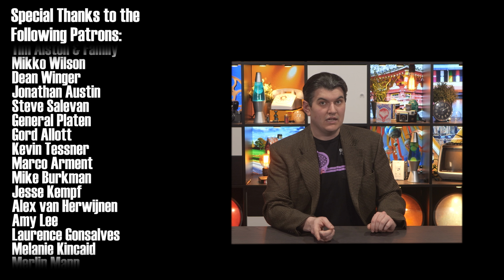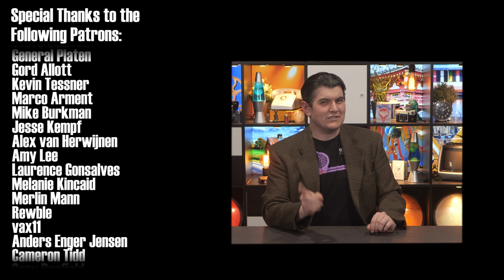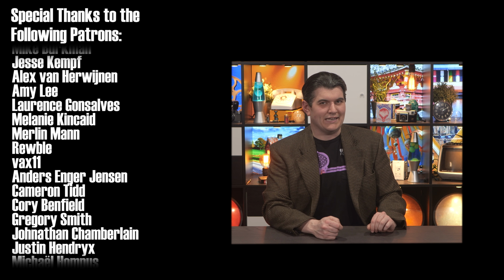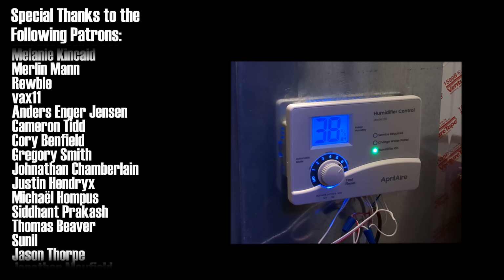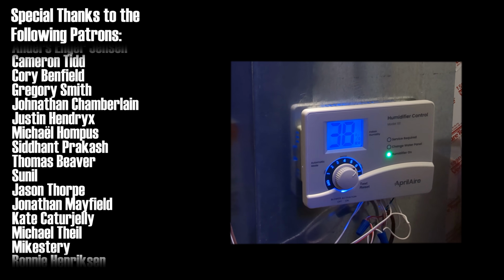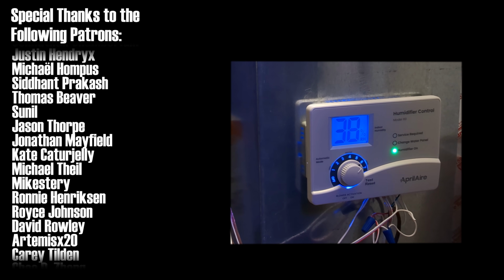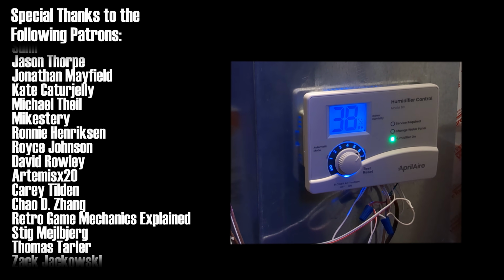Second, at time of filming, I haven't yet verified whether or not it knows the thermostat is commanding the fan. It should, but I didn't think to actually test that before I got here and shot the talking head. Here's the answer: I just confirmed that yes, it does turn on the humidifier when the thermostat gives it a fan call, so that is working as I expected.